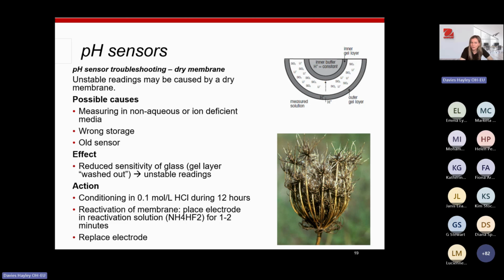You can get a dry membrane if you're measuring in non-aqueous or ion deficient media or solutions. If you've put it in the wrong storage, so if you've stored it in water, for instance, or if it's just an old sensor. An old dry membrane will result in reduced sensitivity of the glass, and the gel layer inside is just washed out. It gives unstable readings, so we can try and condition it. You can condition this in a 0.1 molar HCl solution for 12 hours. So you can pop that in overnight, leave it in that solution to really try to hydrate and reactivate the membrane.